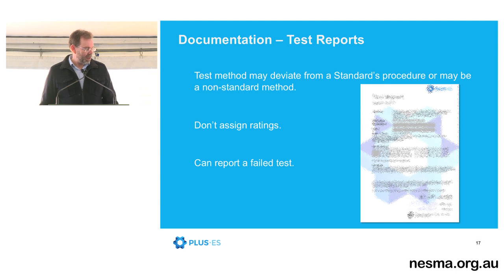In actual fact, customers come to us with their own test methods. They might be doing an investigation or some R&D, so it's not unusual that they'll just have something totally made up and their own criteria, and we can issue a test report on that. But it is interesting to think that if someone gives you a test report for a piece of equipment, it doesn't necessarily mean that it meets a standard, or it could be just their own procedure that they've invented. For that reason, it doesn't assign ratings. A test report is literally just documenting what we did and what the results were. And in actual fact, we can issue test reports for failed equipment.